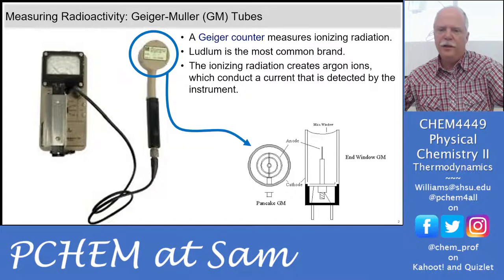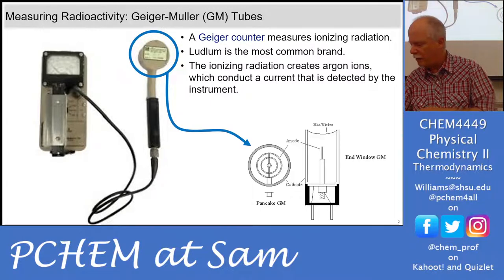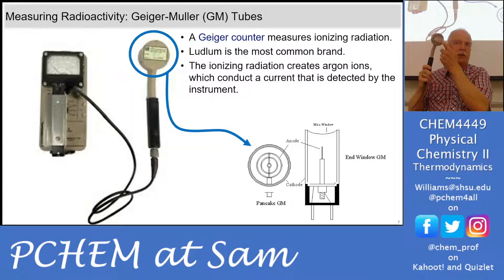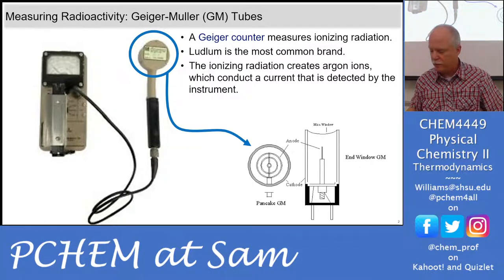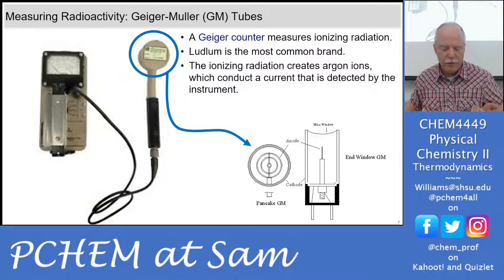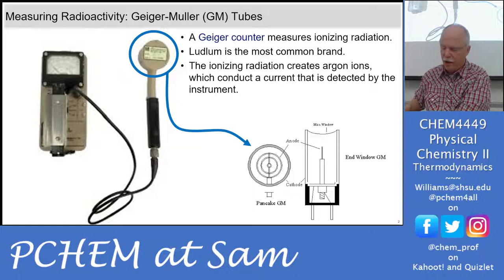We can also look at this in terms of gamma rays. Let's find one that's a gamma emitter — this one says beta and gamma. I'll turn the probe backwards, shooting the radioactivity through the back of the probe. It's measuring 0.3 to 0.4 millirem per hour, so that's the gamma contribution — about 10 to 15% of the beta particle signal. I get right up close to the source and it high-alarms at 15; I back off about an inch and it drops to seven.